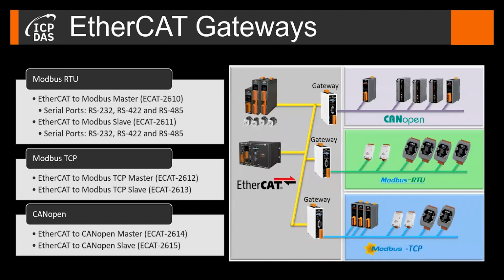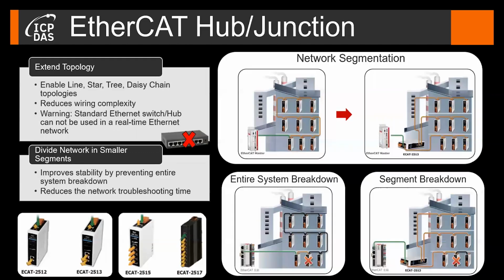EtherCAT gateways allow industrial equipment that does not support the EtherCAT communication protocol to smoothly exchange data with the EtherCAT master. ICP-DAS provides EtherCAT gateways for Modbus RTU, TCP, and CANopen. The gateway acts either as a slave or as a master in the local network. The gateway allows the connection of just one module, like a Modbus or CANopen module, or a network of Modbus or CANopen slaves.